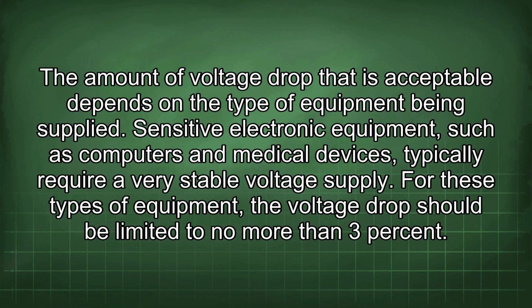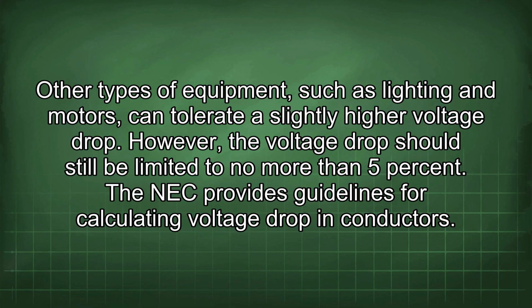The amount of voltage drop that is acceptable depends on the type of equipment being supplied. Sensitive electronic equipment, such as computers and medical devices, typically require a very stable voltage supply. For these types of equipment, the voltage drop should be limited to no more than 3%. Other types of equipment, such as lighting and motors, can tolerate a slightly higher voltage drop. However, the voltage drop should still be limited to no more than 5%.